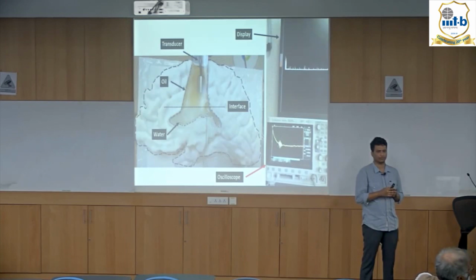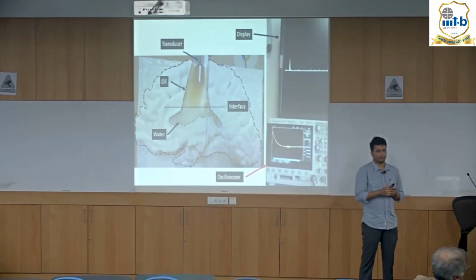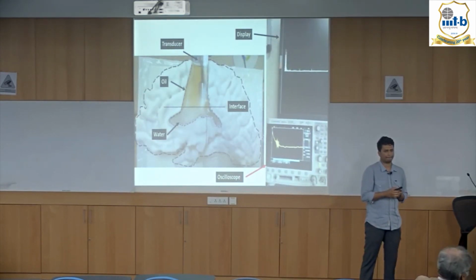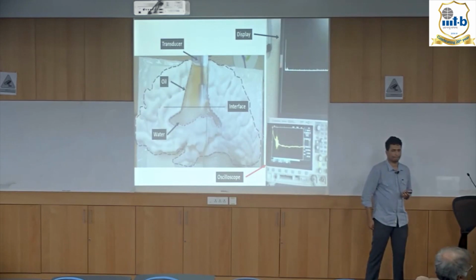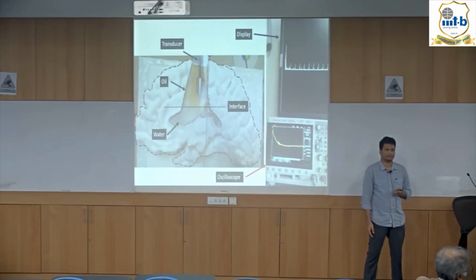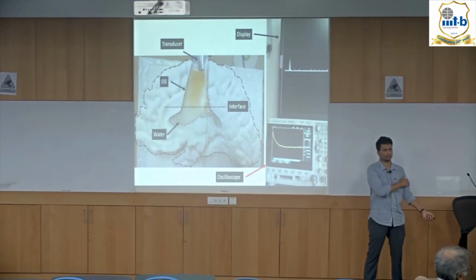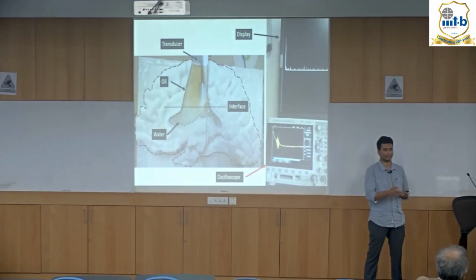The transducer has to become smaller, and the frequency has to be adjusted also. High voltage anyway you need to excite those. You need more energy because the echo is lower, Professor. Because the echo strength is lower, we increase the input voltage so that we get a stronger ultrasound pulse.